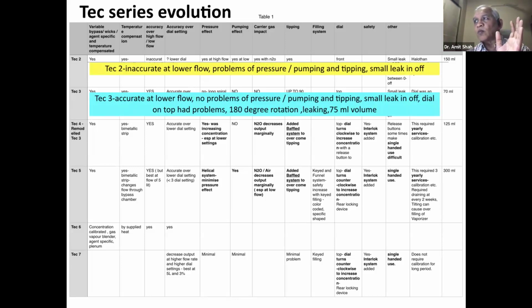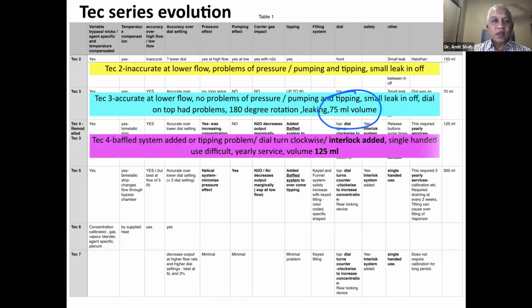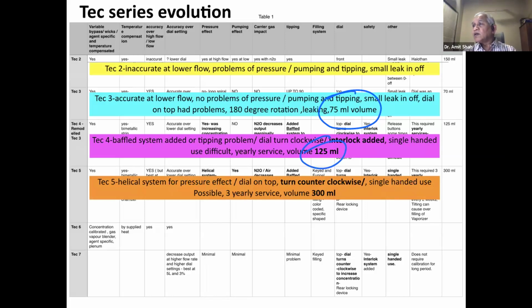In Tec 3, they improved accuracy at lower flow. No pressure or pumping, tipping problem, but there was still a small leak. The volume was actually less, okay? And the rotation was more, a 180-degree rotation of the dial. Tec 4 added the baffle system, which we understood, the compartment and the wicks. It avoided the tipping problem. Then we realized that turning the dial clockwise was actually hazardous. So we started making it counterclockwise. So the dial was turning clockwise earlier, then it started turning counterclockwise. An interlock was added. It was single-handed use, and the volume was increased to 125. In Tec 5, the dial is turned counterclockwise, and the volume was increased to 300 ml.